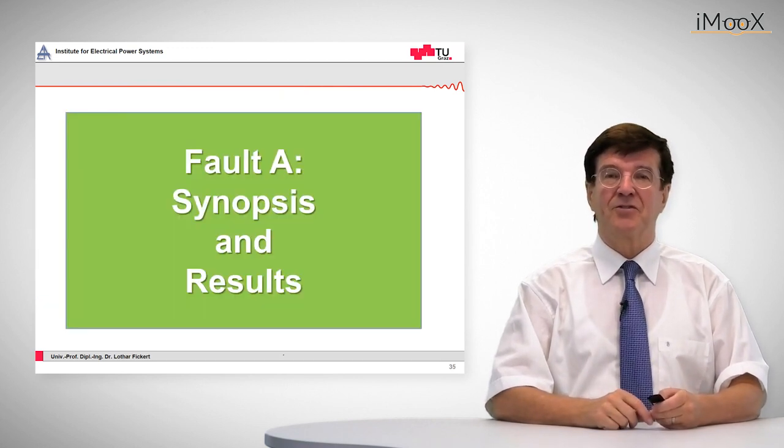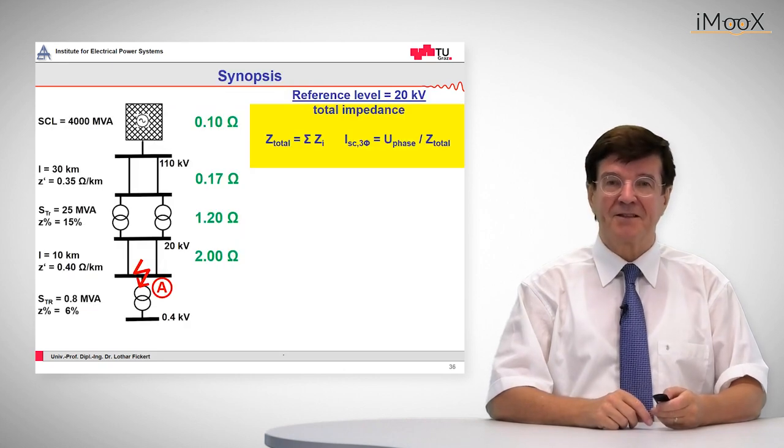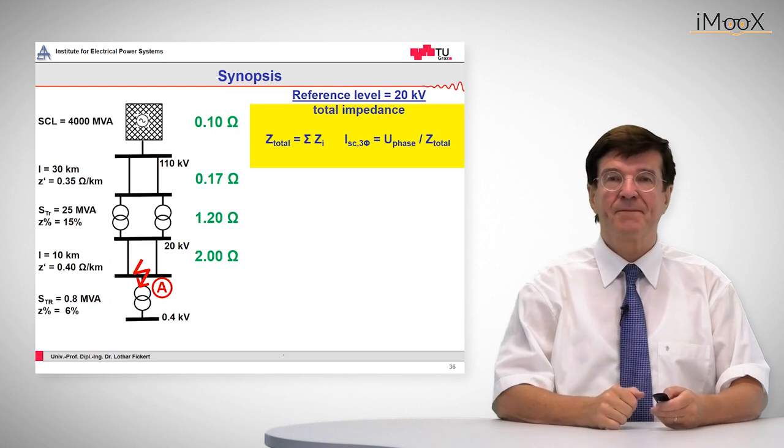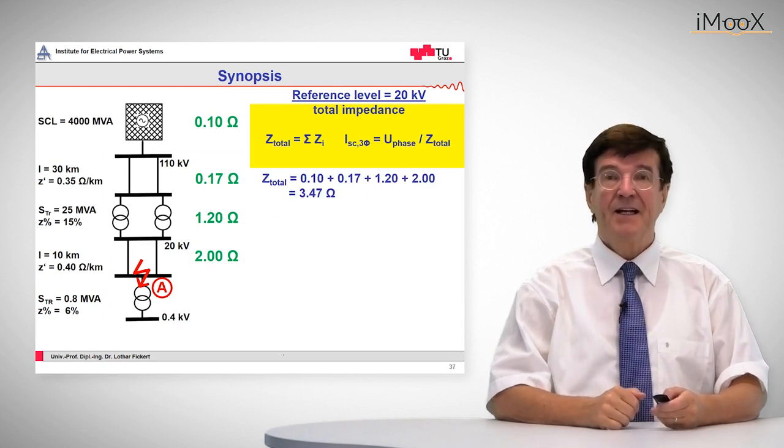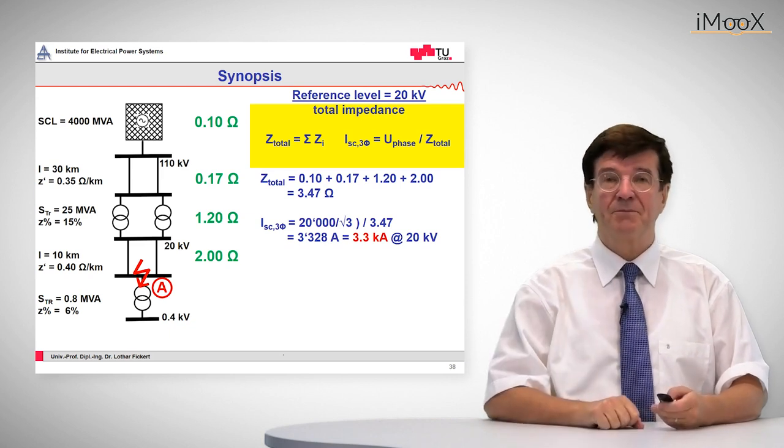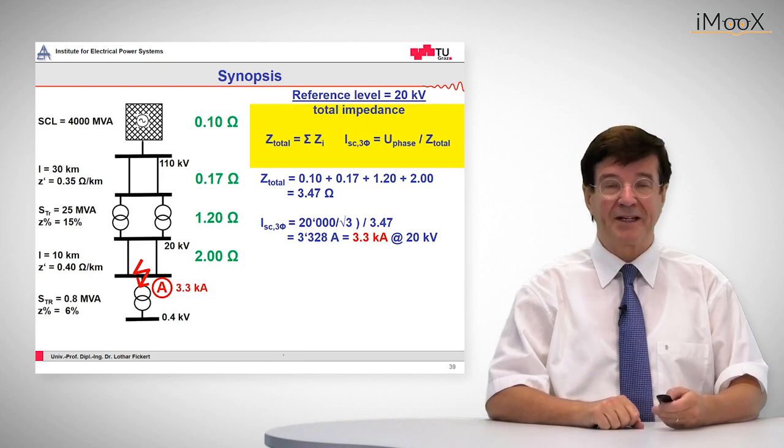So now we can go to the synopsis and take the result. Synopsis means we add up all these impedances, which gives 3.47 ohms, and we have to divide the phase voltage for three-phase fault by this value, and what comes out is a current value of 3.3 kiloamps.